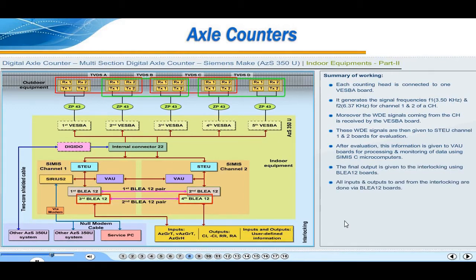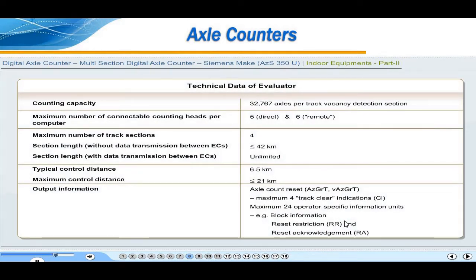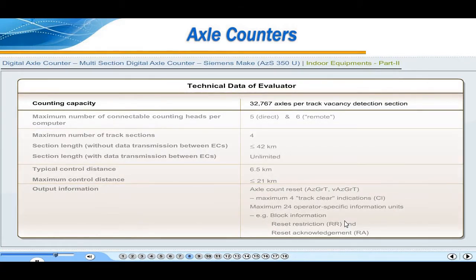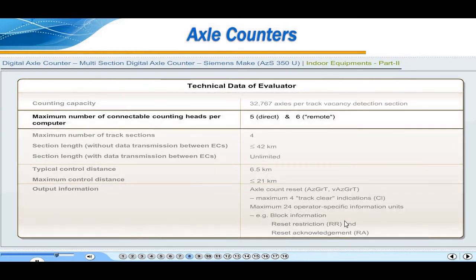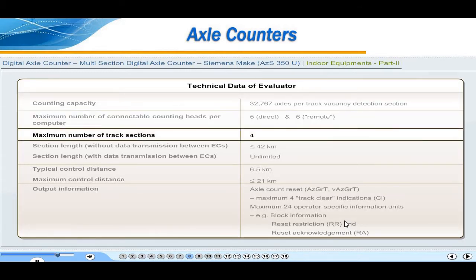All inputs and outputs to and from the interlocking are done via BLEA12 boards. For transmission of WDE signals between two AZS350U units, SIRIUS2 board is used. For WDE signals to be jointly used between two evaluation computers, Digido board is used. Technical data of evaluator. Counting capacity is 32,767 axles per track vacancy detection section. Maximum number of connectable counting heads per computer is 5 directly and 6 using remote control. Maximum number of track sections is 4.